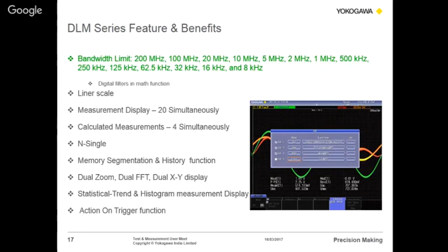And you can plot a trend or histogram measurement display. And action on trigger - in particular, you can set, like if voltage goes more than 30 volts or 40 volts, you can set the trigger levels. So if that signal reaches that particular threshold, it will capture. That is the action on trigger.